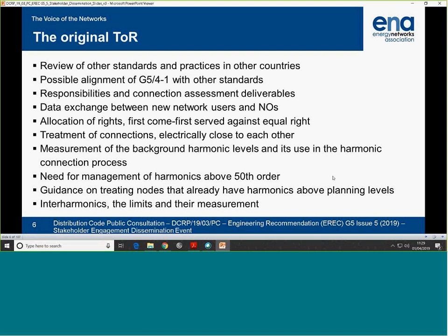And therefore, how you allocate headroom in the network to these connectees was a big issue. Connections electrically close: when you get a large number of connection applications, then if close, how do you deal with them? That again was another issue. Measurement, how do you do it, and what standard do you use? The need for management of harmonics above 50th was a big issue because, as I said, we're now getting connectees with IGBT-based technology, which emit, according to supply, harmonics above 50th.